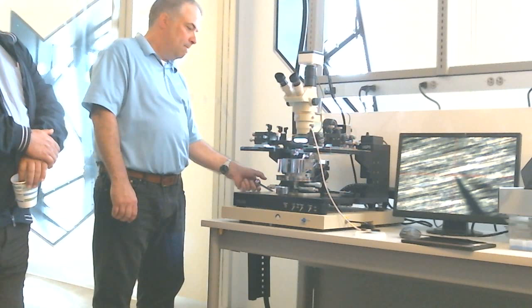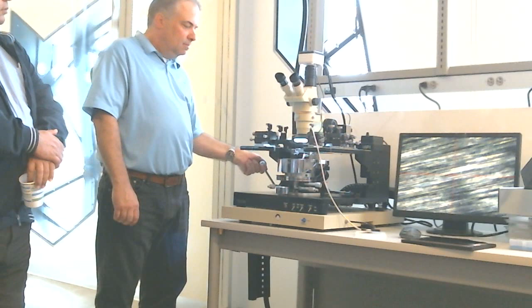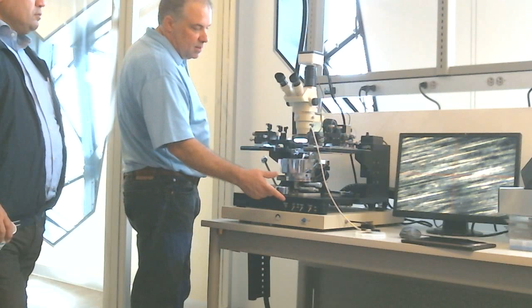You mean this lift? No, there was a vacuum switch which apparently locks the chuck, does it not? The button on the left side of the chuck will activate the air for the air bearing, and when you release it, it will apply vacuum, so this will be locked. And then there's the vacuum for your substrate for your chuck vacuum. It'll lock your sample down to the surface. Did that answer your question? But in case it accidentally moves, don't do that. If you've got your probe down and you accidentally move something, hit something, then don't bump into the arms.